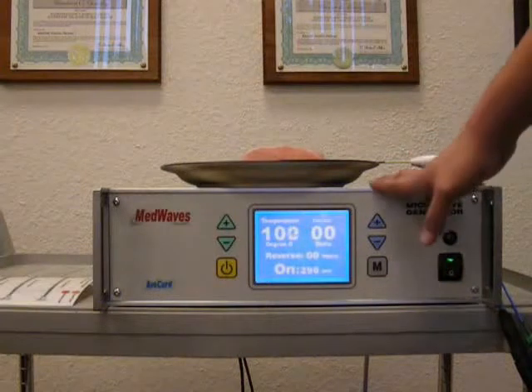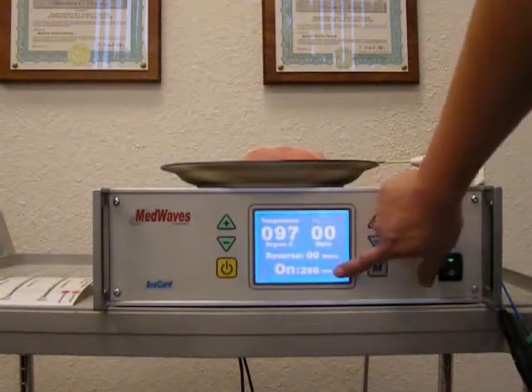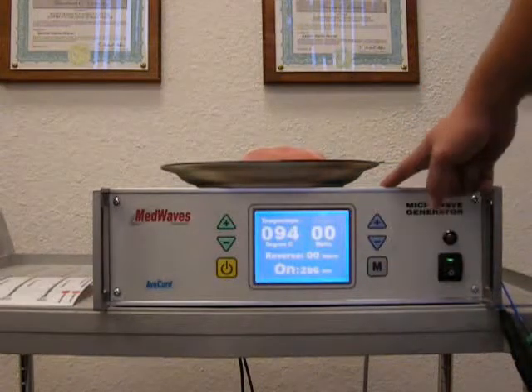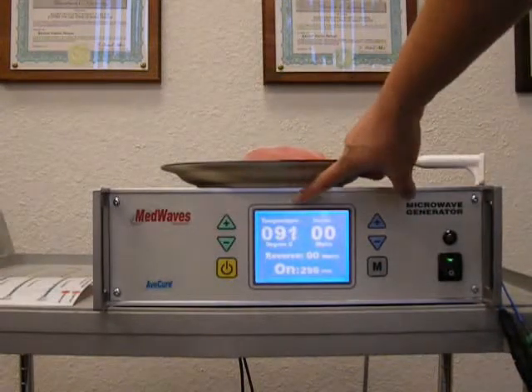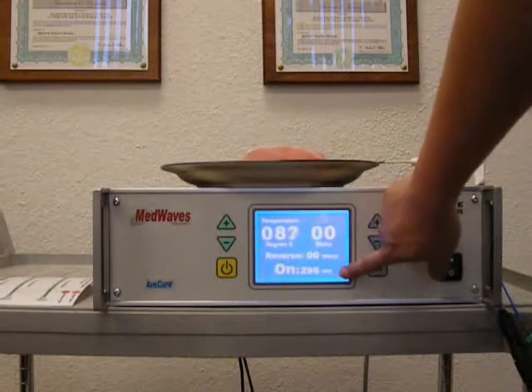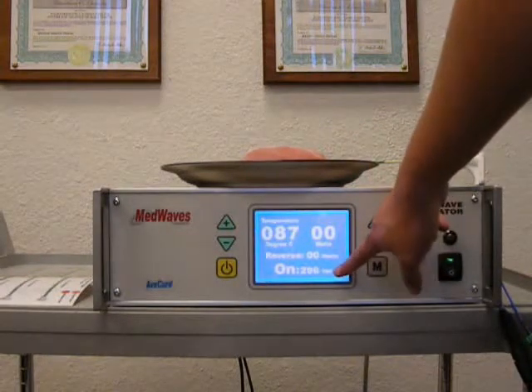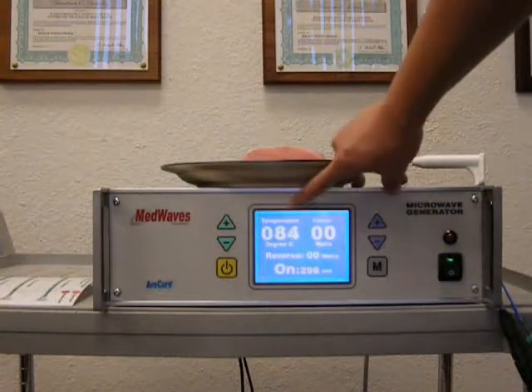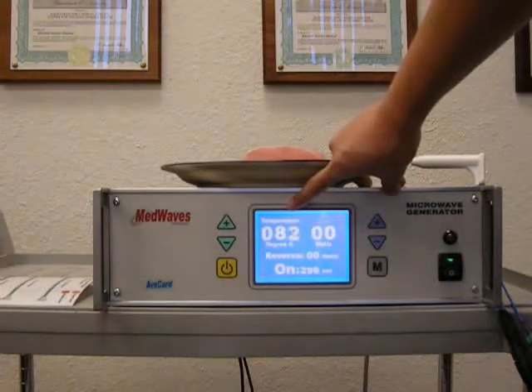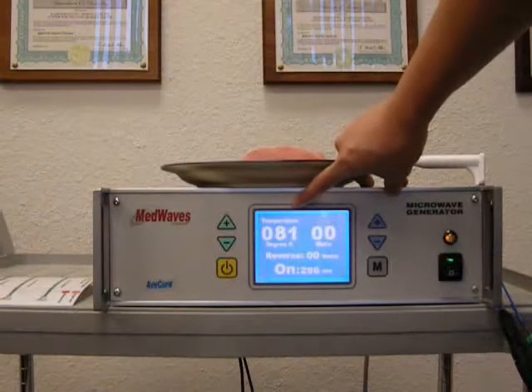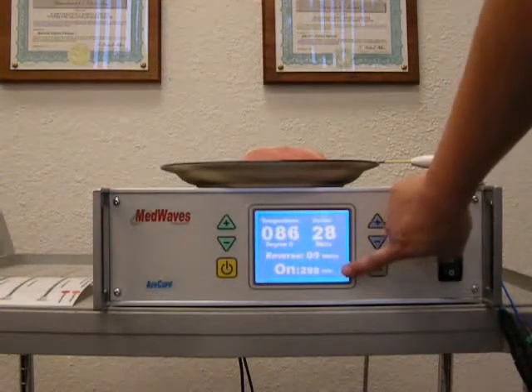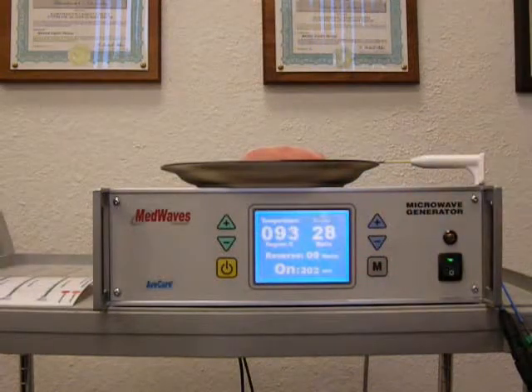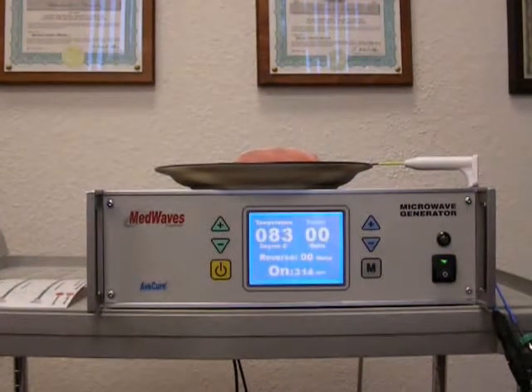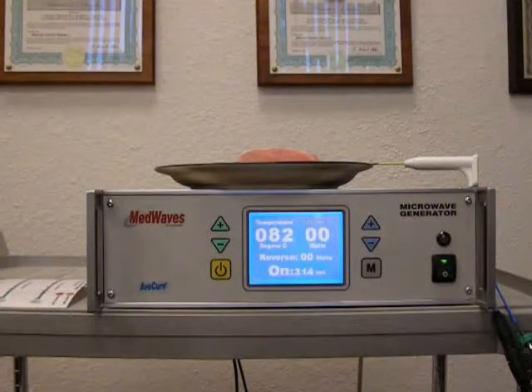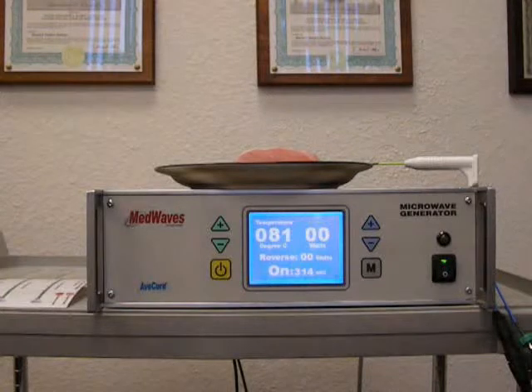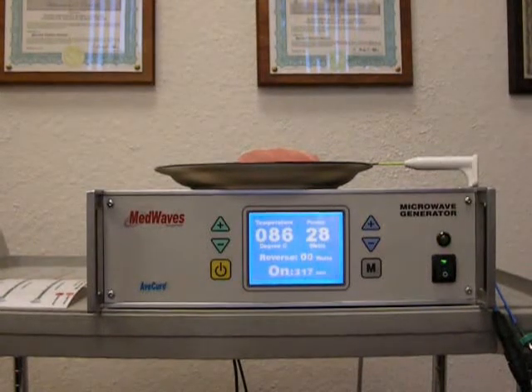Also in power control mode, when power is not being delivered, the ablation time will not count. So in this case, as the temperature is dropping down to 80, the time of ablation remains at 296 seconds. Once the temperature drops to 80 and the power comes back on, then the timer will start again. In power control mode, this cycle keeps repeating until the total time is up.